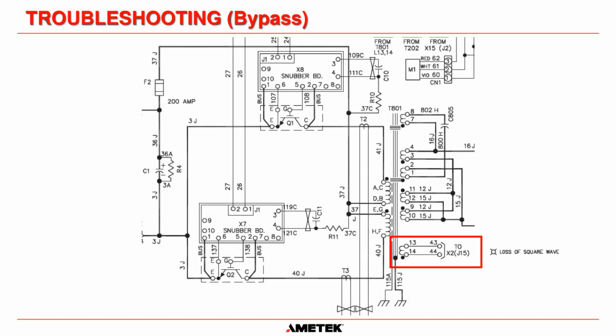So what we have is a loss of square wave circuit that says, okay, if the square wave fails going into this primary side of the transformer, we want to transfer the system to bypass while we still have that stored energy in the transformer. If we waited and measured the output of this side and waited for it to fail, then we would be transferring to bypass as the system is failing and doesn't have the stored energy.